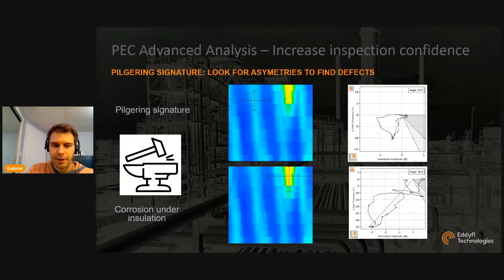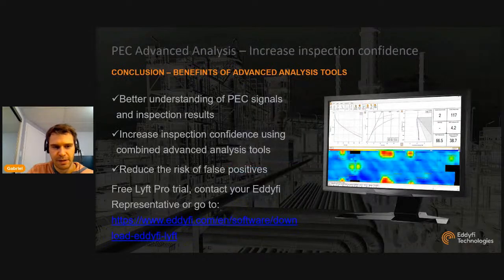But when you look at a real indication such as this one, the real indications within the Pilger signature are also well identified as defects. So it's a case where you need to look for asymmetries in the C-scan to find defects, areas where you've got more wall loss or the wall loss is standing out from the pattern of the pilgering signature.